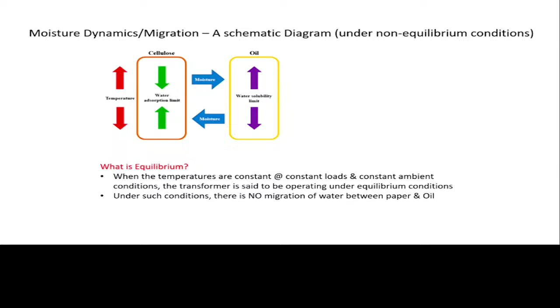The moment the music stops, that's what we call a non-equilibrium state in a transformer — meaning the temperature is either going up or down. As long as temperature is constant, the music is on. When temperature rises, due to load increase, or falls due to ambient conditions dropping to 20 or 10 degrees as in Western countries, you disturb this equilibrium. That's when all hell breaks loose — like in musical chairs, people try to occupy whichever chair is vacant, and one of them loses out, and so on.